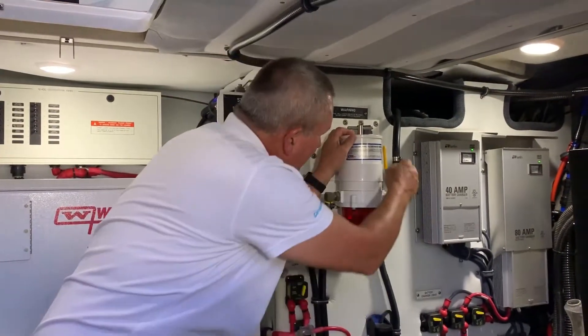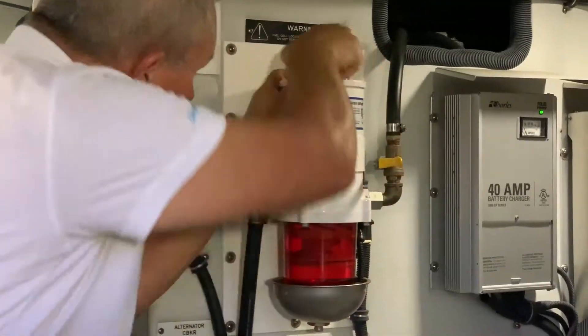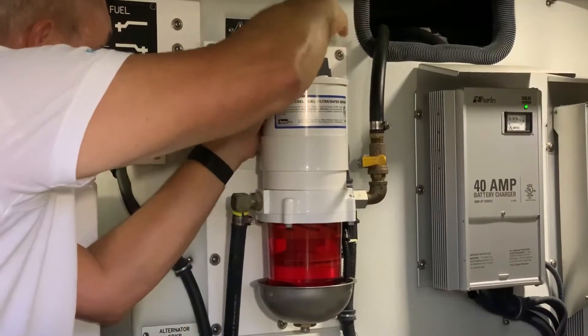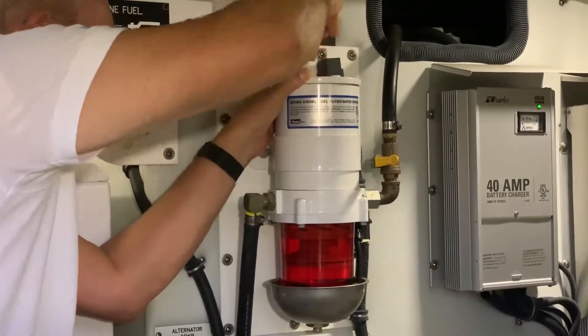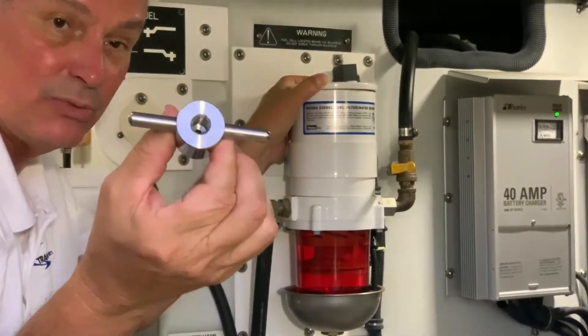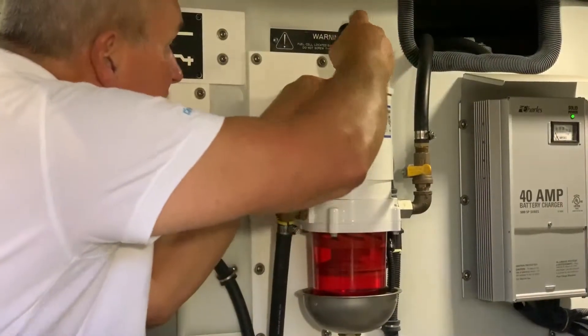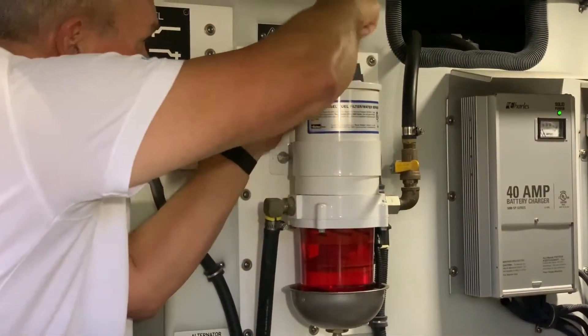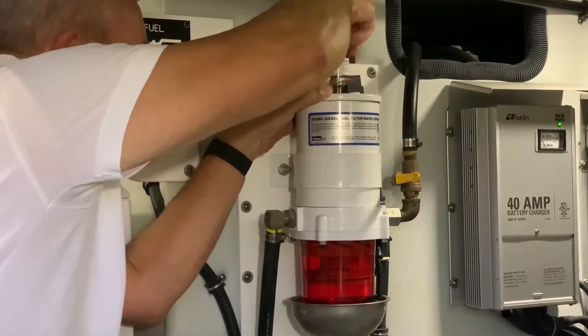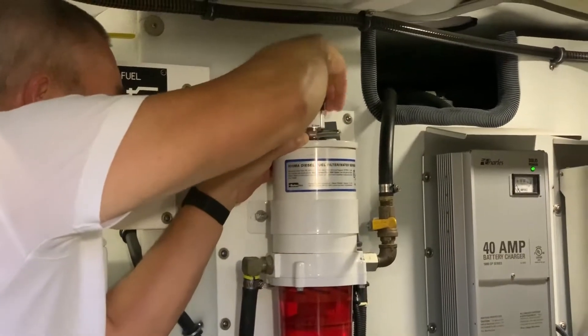So the first thing we're going to do is come over to our fuel filter water separator. In this case we're going to shut our fuel valve off and crank this little T-handle out of here. You can see the length of the threads. Sometimes you'll actually see a device like this — a little T-handle with a little hole up on top that has an antiquated mechanical pressure gauge, about 10% accuracy. The new FF version is actually a 1% device, ten times more accurate for remote readings.